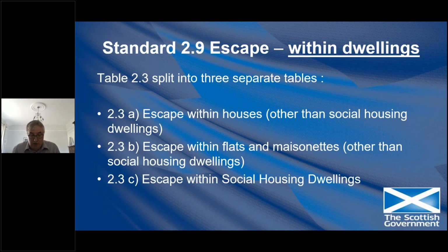Clause 2.9.2, table 2.3, escape within dwellings, has been split into 3 separate tables in standard 2.9. This includes 2.3a, escape within houses other than social housing dwellings. The guidance for escape within houses has remained unchanged, and as you can see, social housing dwellings now have their own table at 2.3c.